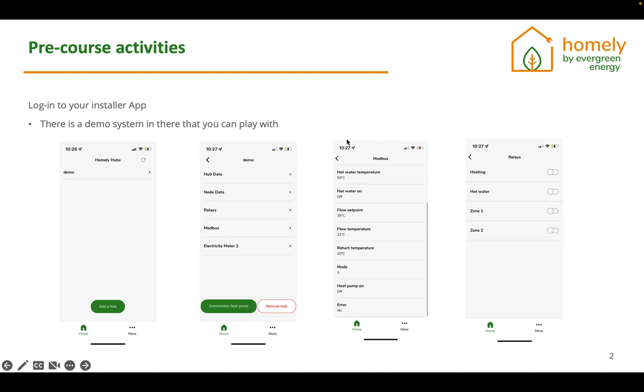Modbus section. This allows you to see the real-time data of the heat pump. Here you'll see the different temperatures in terms of flow, return temperatures, hot water temperatures, as well as whether there is an error. So if a customer calls up and says that there is an issue with their heat pump, you can actually go into your installer app and check whether there's an error. At the moment, it will say yes or no. In the future, you'll be able to see what that error code actually is.